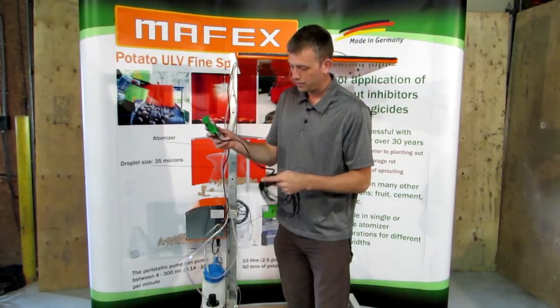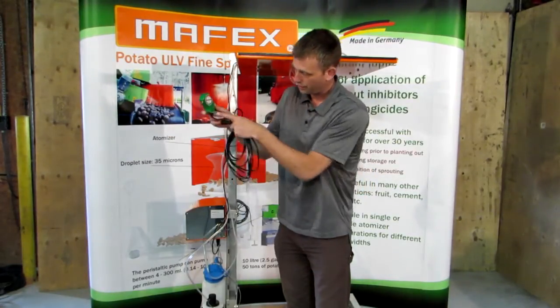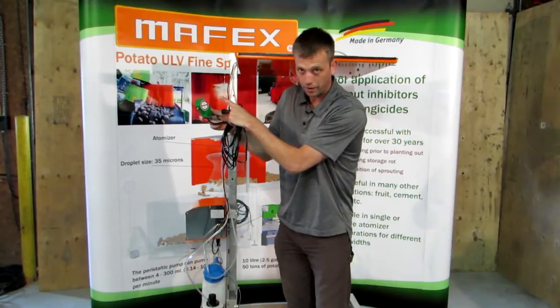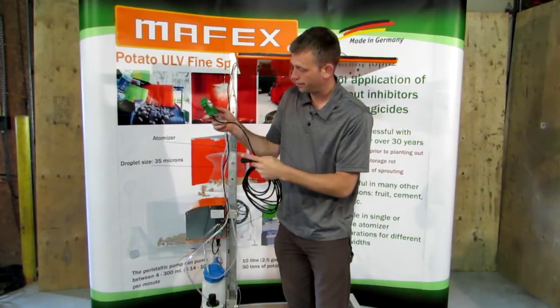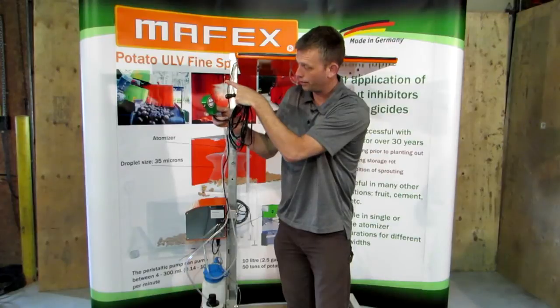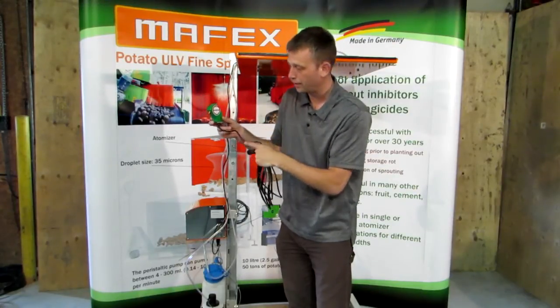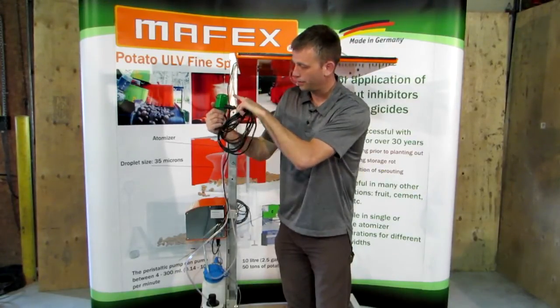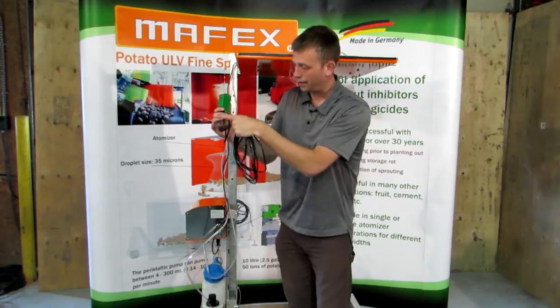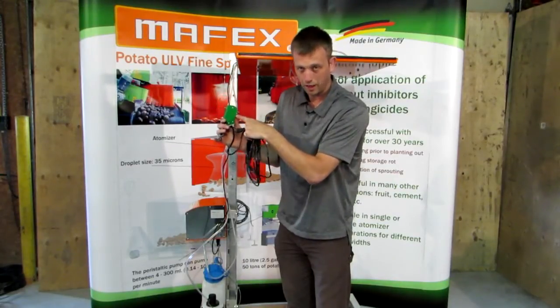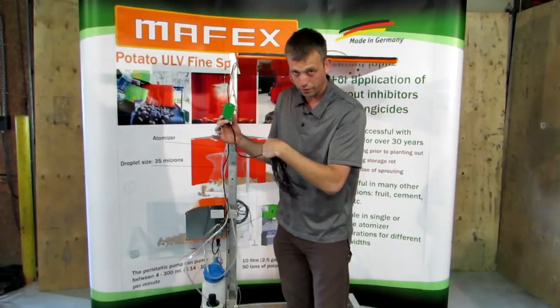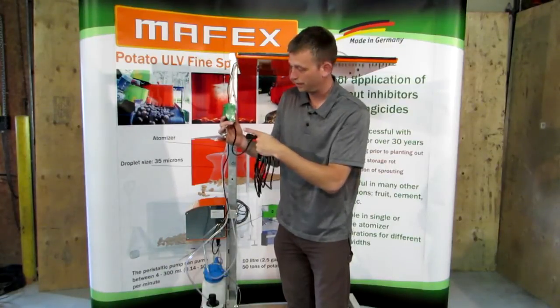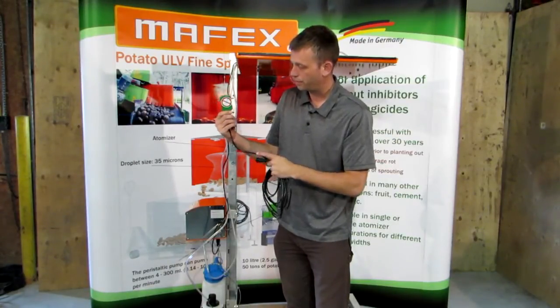So normally speaking, the best way to do this is to make sure that the liquid is flowing uphill through the flow sensor to a high point and then down to the atomizer. If we're flowing downhill to an atomizer, what will happen is we'll get continuity problems because the liquid will just flow through too quickly to make contact. So it's best to be pushing uphill.